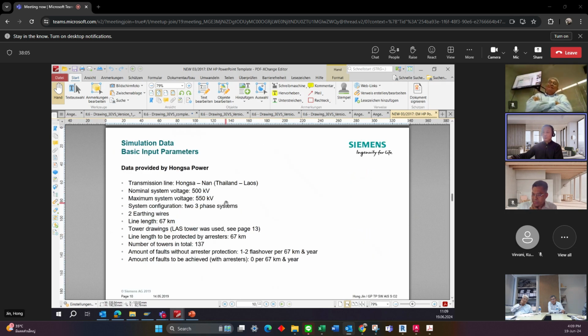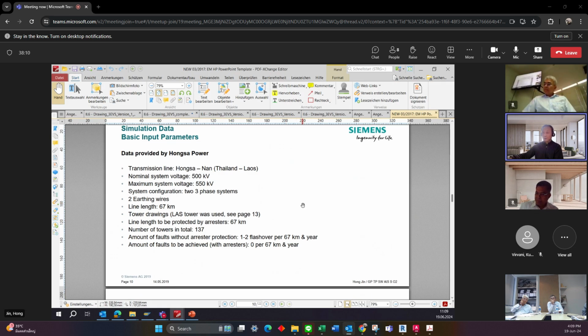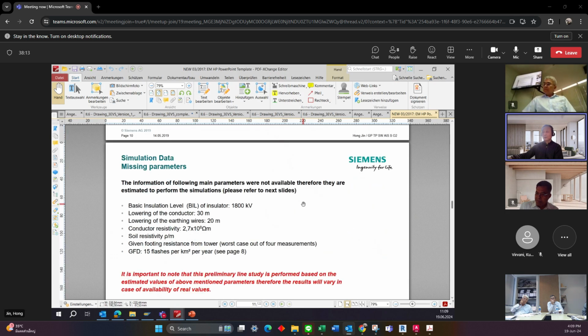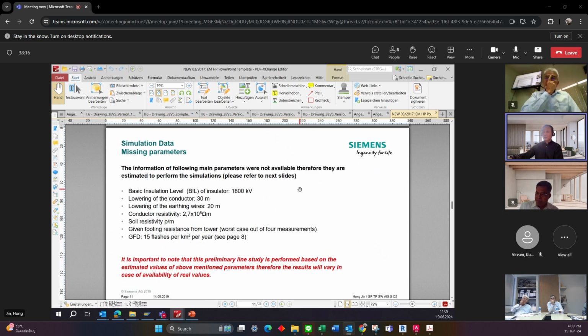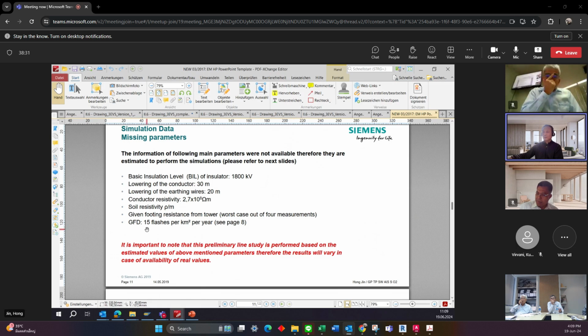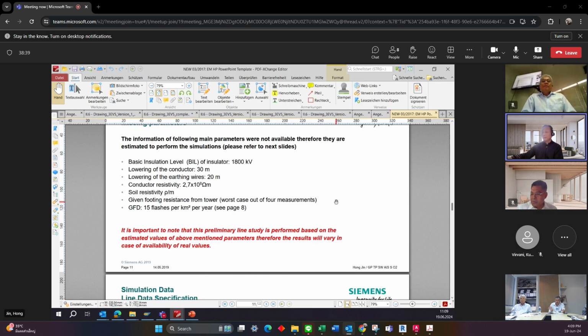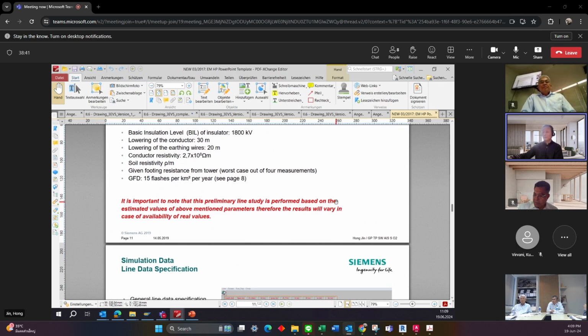So this is the basic information from Hongsa to Nan, and we received all those data from the customer. And also the current situation without the surge arrester protection, how heavy the tripping failure is now. Currently, before the installation of the EGLA, they have 15 flashes per square kilometer per year, and this is the ground flash density.